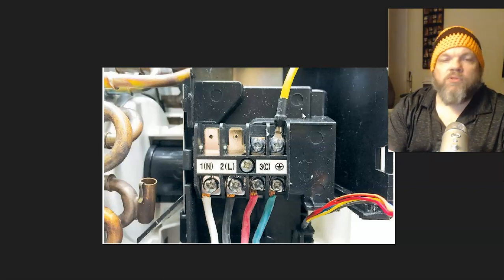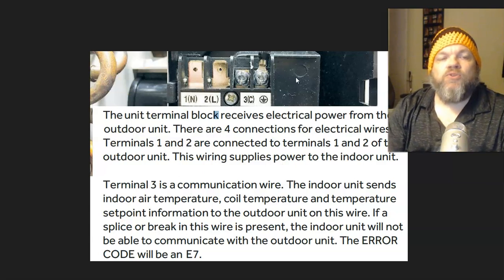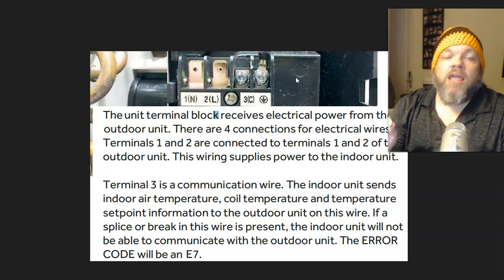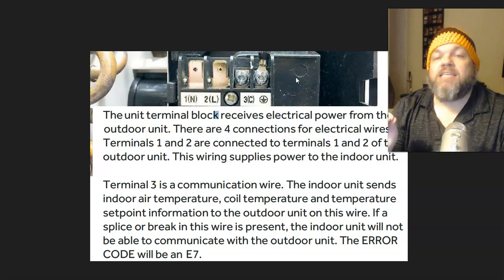To go further with what the manual says from Haier: the unit terminal block receives electrical power from the outdoor unit. There are 4 connections for electrical wires. Terminals 1 and 2 are connected to terminals 1 and 2 of the outdoor unit, and this wiring supplies power to the indoor unit. Terminal 3 is a communication wire - the indoor unit sends indoor air temperature, coil temperature, and temperature set point information to the outdoor unit on this wire. If a splice or break in this wire is present, the indoor unit will not be able to communicate with the outdoor unit, and the error code will be an E7 error code.